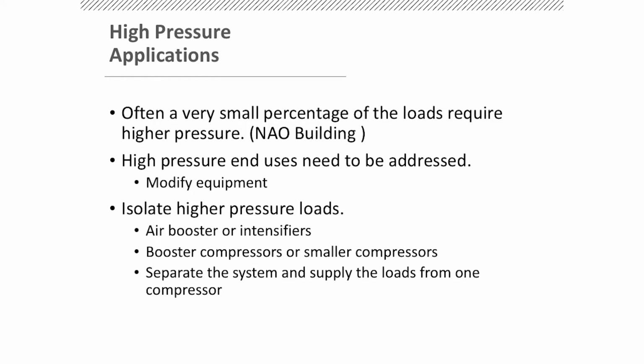What do you consider high pressure? Good question. What would you consider high pressure? Well, if it was the plants in Europe, they have an 8 bar and a 12 bar, which is basically 90 to 100 psi and 130 to 140 psi. But when we talk about high pressure, it's really a relative pressure. What is the highest pressure you use in the system that's causing you to keep the pressure at that elevated state? I had one division where high pressure for them was 80 or 85 pounds because they were trying to get to 60 pounds. So for the transmission and engine, they were specifying that they want all equipment to come in at 60 to 65 pounds max because they want to lower all their pressures.